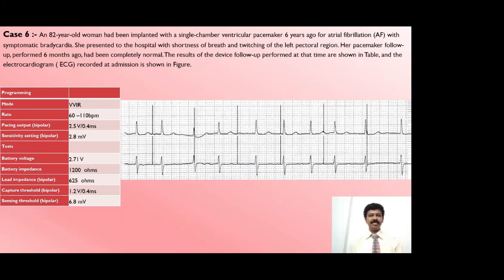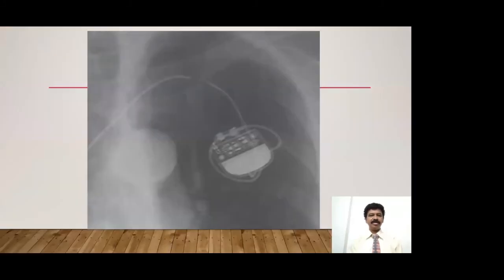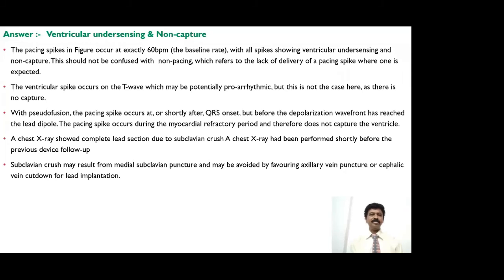This is a single chamber VVI mode, and this happens after a few years or some time after implant. Classical subclavian crush syndrome, you can see that in the X-ray. So you cannot capture. So this is an emergency. You need to redo and reinsert the lead and then check the device.